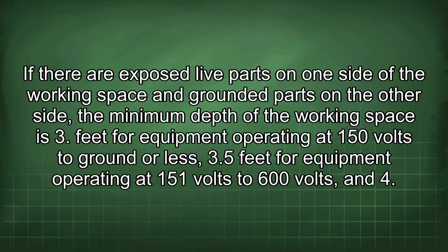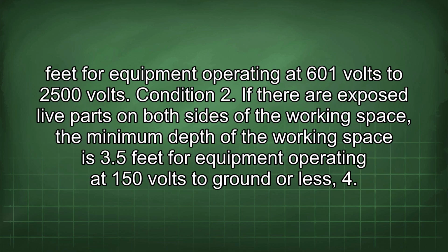Condition 1. If there are exposed live parts on one side of the working space and grounded parts on the other side, the minimum depth of the working space is 3 feet for equipment operating at 150 volts to ground or less, 3.5 feet for equipment operating at 151 volts to 600 volts, and 4 feet for equipment operating at 601 volts to 2500 volts.